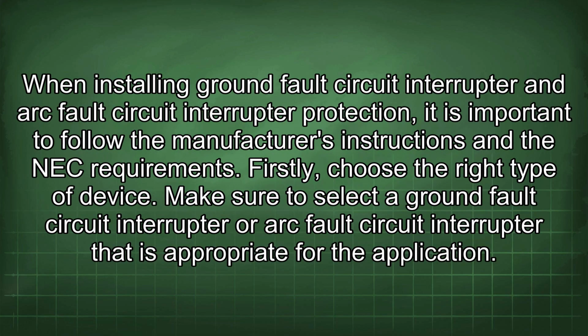When installing ground fault circuit interrupter and arc fault circuit interrupter protection, it is important to follow the manufacturer's instructions and the NEC requirements. Firstly, choose the right type of device. Make sure to select a ground fault circuit interrupter or arc fault circuit interrupter that is appropriate for the application.